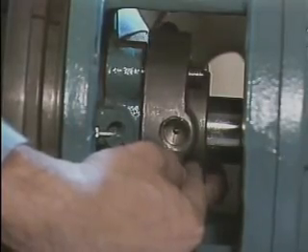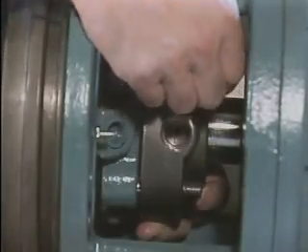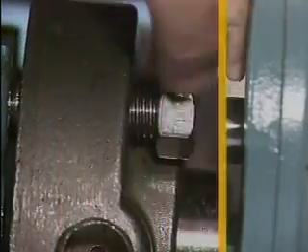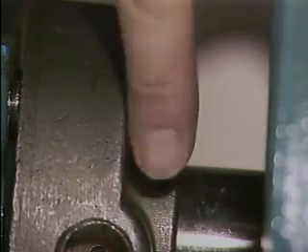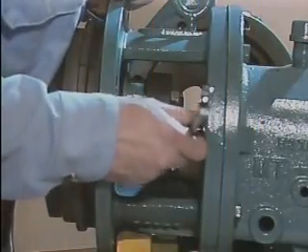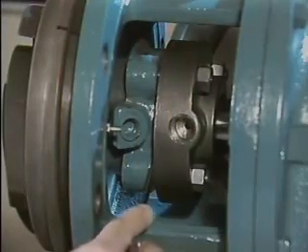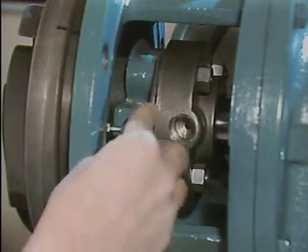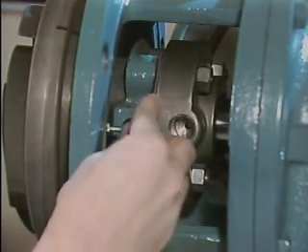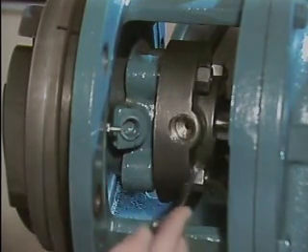If the clearance is correct, the gland plate can be secured. The plate is slid along the shaft toward the stuffing box. The gland plate nuts are then installed and tightened until the gland plate is snug against the stuffing box. Over-tightening these nuts could warp and damage the mating ring. To ensure that the nuts have been tightened uniformly, the gap between the gland plate and the stuffing box is measured at each gland plate bolt. If the gland plate is properly installed, the measurements should all be the same.